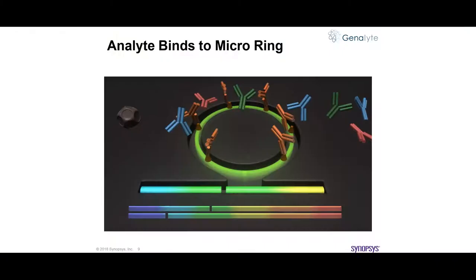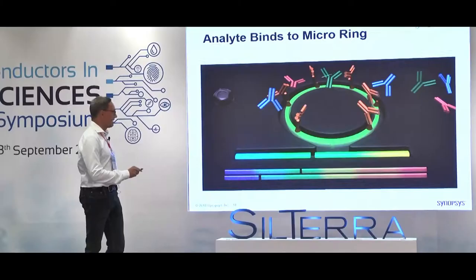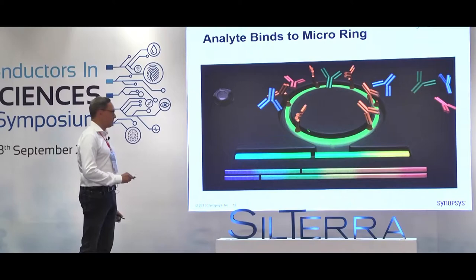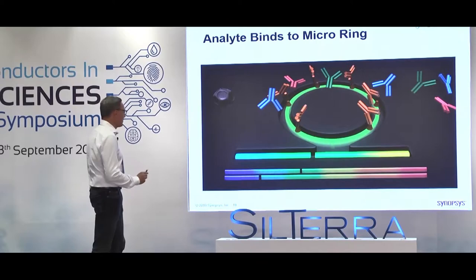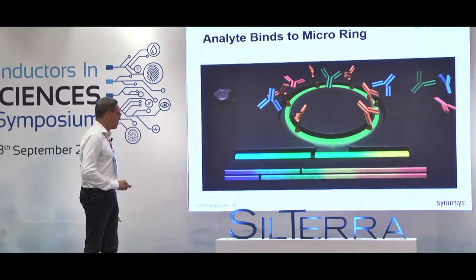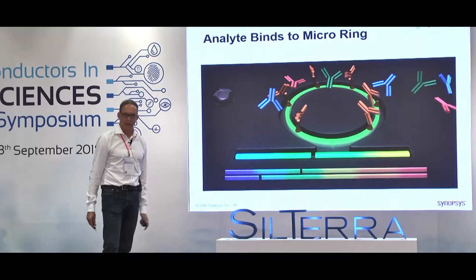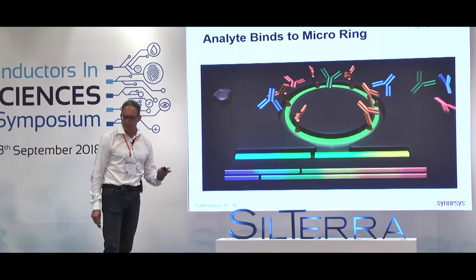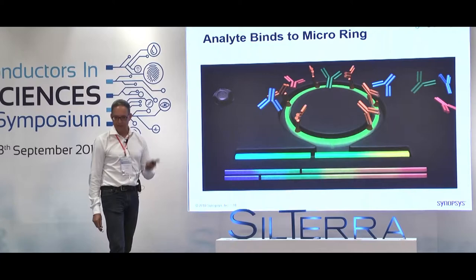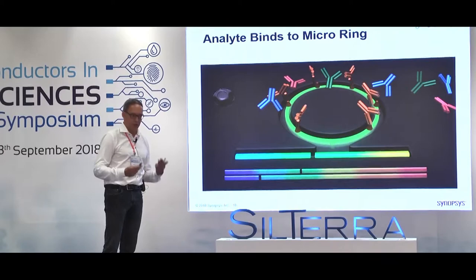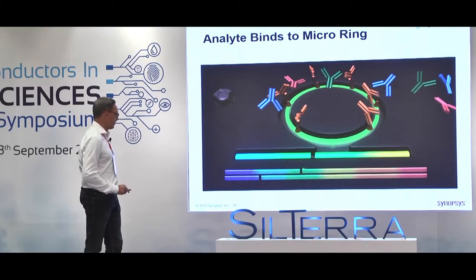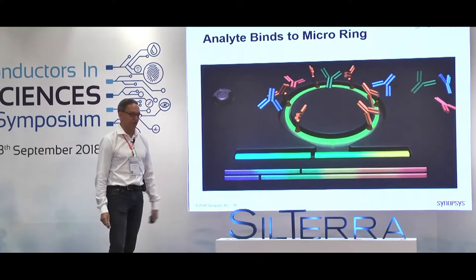If you look at the end of the straight channel and analyze the spectrum, you will see a notch — you're missing the light there, and that's your resonance wavelength of the ring. Now you start flowing the microfluidic channel across it. The channel has all the analytes in the fluid. This ring is functionalized for specific analytes. It's like organ pipes in a church: if you spray paint them, the tone changes. The analytes bind to the ring, adding mass, and the frequency of the light changes — so you see your notch shifting.